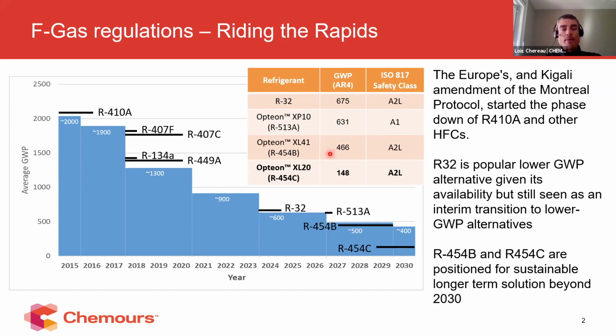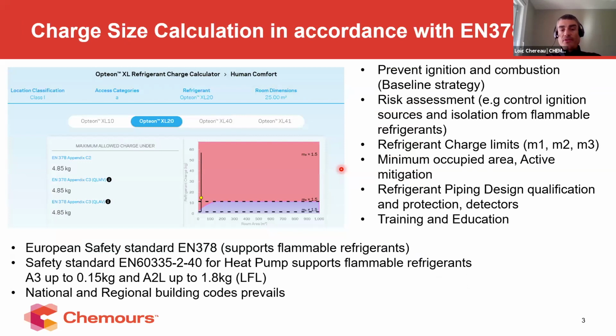There are, of course, some differences also between use in a direct expansion system or an indirect expansion system. And let's say, for instance, for an indirect expansion system, like chillers, if they are used outdoors, there is no mitigation that is needed, and there is no limitation in terms of charge size that can be used for these refrigerants. So there are different standards to comply with when we look at A1, A2L, and of course A3 flammables.